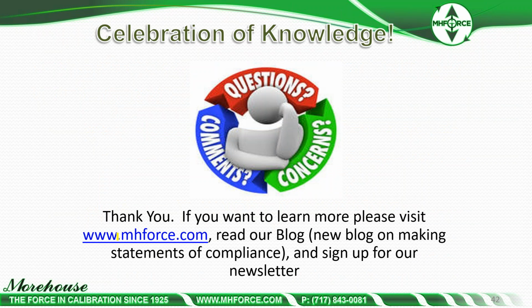If you want to learn more, we have a blog. We have a new blog on making statements of compliance. Wrote that about a week ago. Explains what's needed to make a statement of compliance, a pass, fail. There's some instruments where you cannot make a statement of compliance because the risk is too high, and that's instrument dependent, where the instrument has resolution that's too coarse, or the instrument does not repeat well.